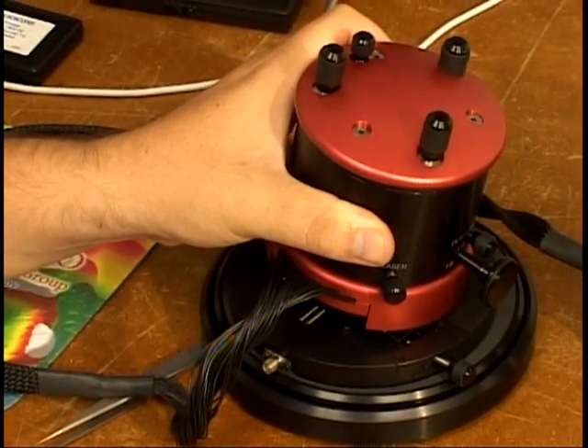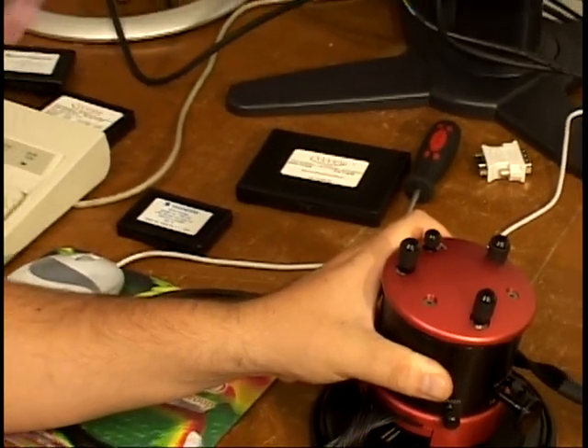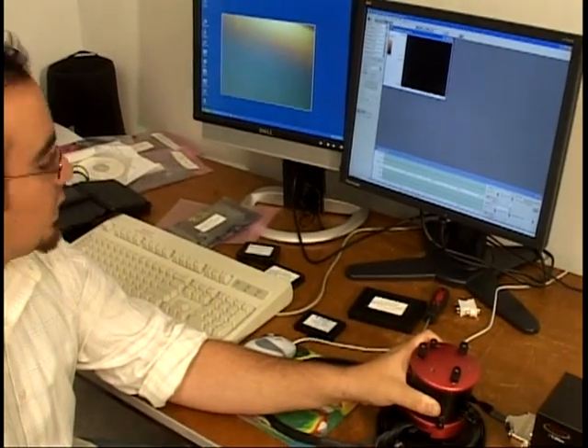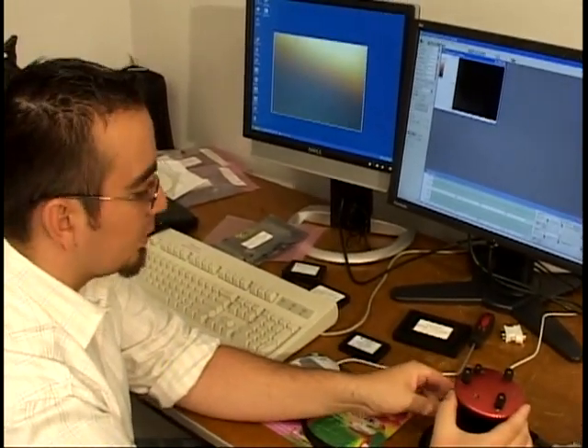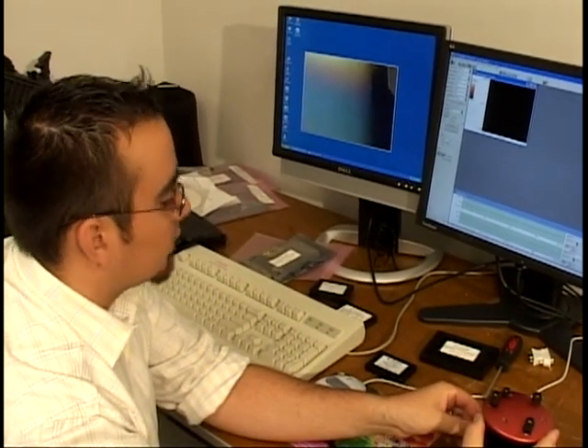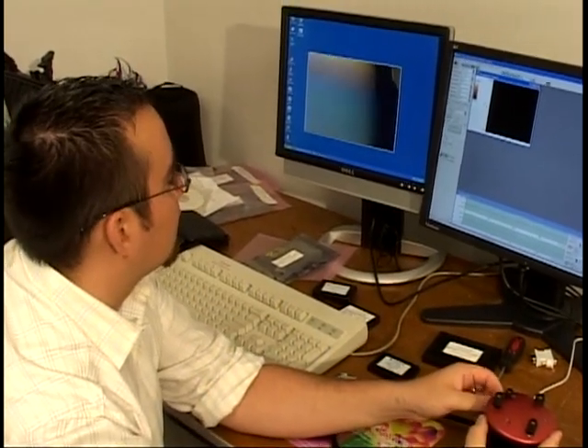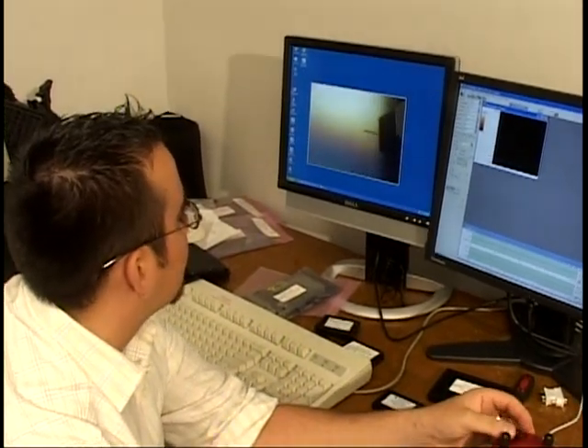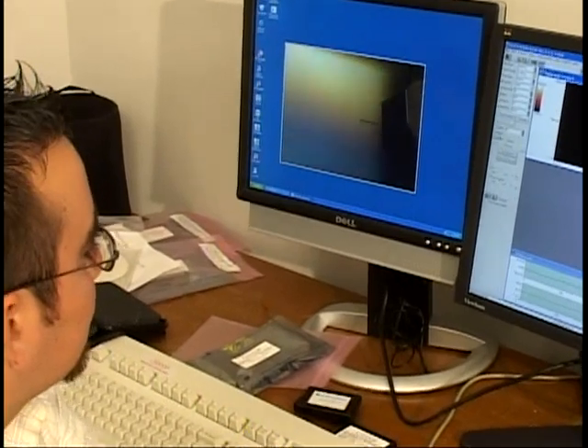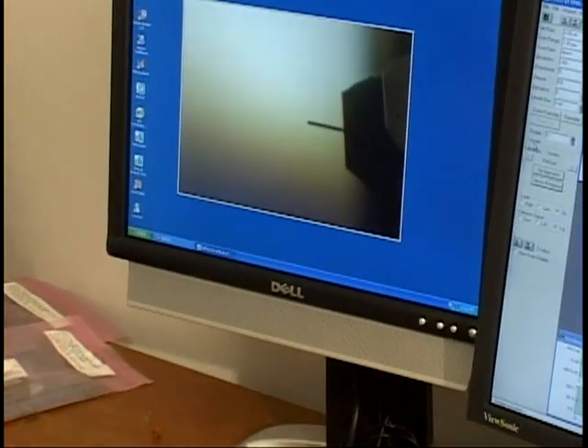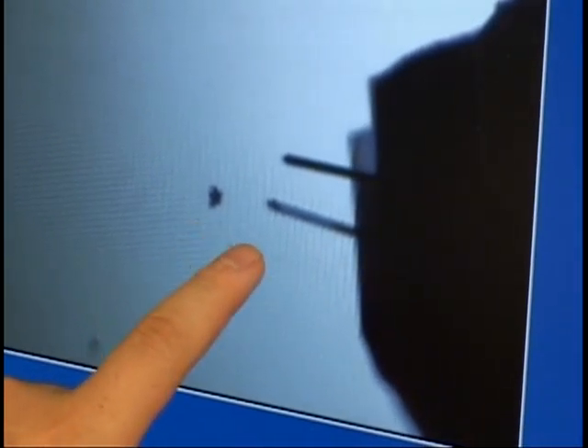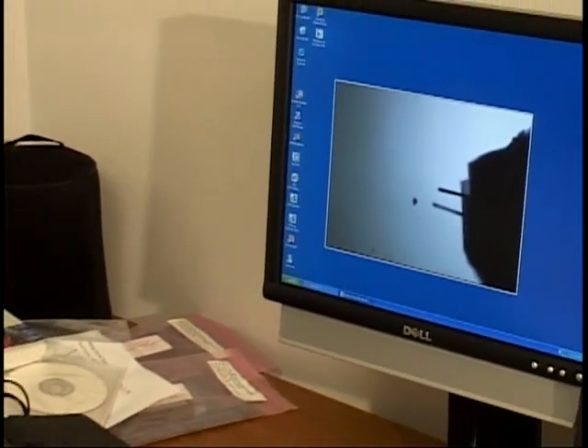So after you do that, you want to be able to look as you lower it onto the probe, which we can't see right now. So until you're able to see it, you can move the probe until it's in focus. Then lower it, making sure you're not going to hit the surface. So close. And we didn't hit it because we can still see the shadow underneath. So the video image won't work very well on non-reflective samples. So if you have a non-reflective sample, it's going to be a little bit harder.